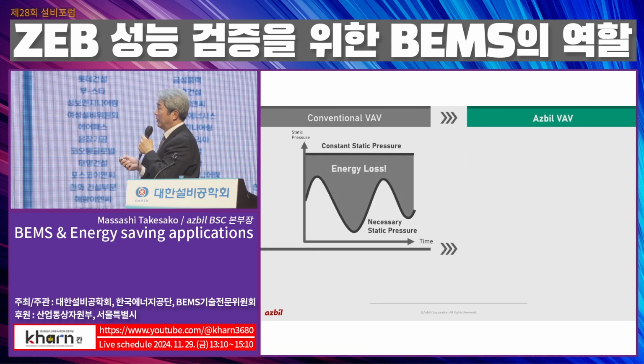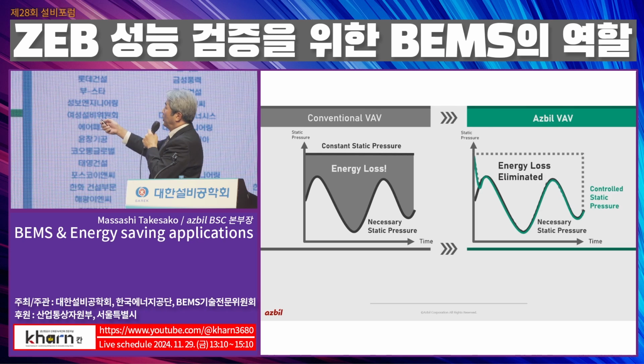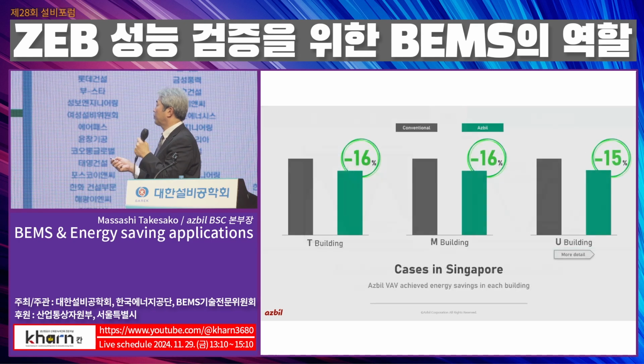Then this is one conventional method. Even though the load fluctuates, the fan static pressure is always constant. This is causing energy losses. Our control method dynamically changes the static pressure according to the load fluctuation. So this is the difference, and we are now providing this to our customers. This is the actual result: 15 to 16% can be saved from normal VAV control to advanced VAV control.